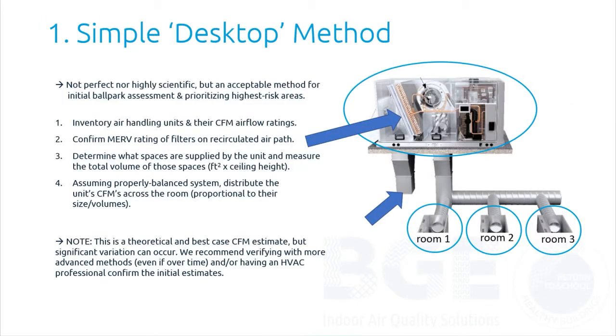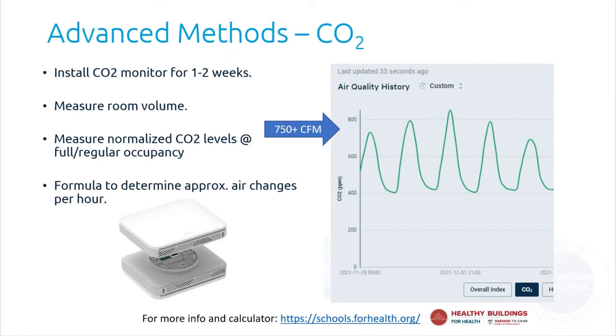The simple method, they call it. It's not highly scientific, but it's a good place to start. Inventory the air handling units and the CFM, the volume of air they're creating, with the MERV rating. Then look at the spaces it supplies and figure out the volume of those spaces, and then you can do the math. In this case, you would assume that the rooms are equally balanced. In real life, they probably aren't, but just for this case, you would do that. It's not scientific per se, but it's a good starting place, and it should give you a good idea of where you're at. There are a couple of other, advanced methods.